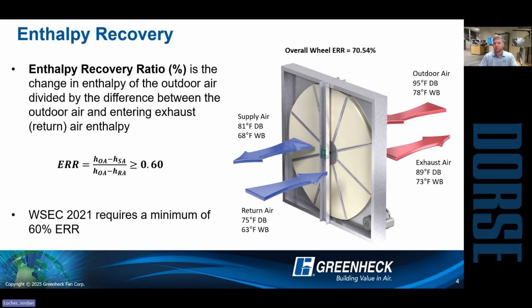Big thing with enthalpy recovery: the easiest way to spot ERVs is that they do not have condensate drains. We are transferring the moisture from one airstream to the other. We're not condensing it out of the air. Across North America, enthalpy recovery is a really great technology and provides a lot of benefits.